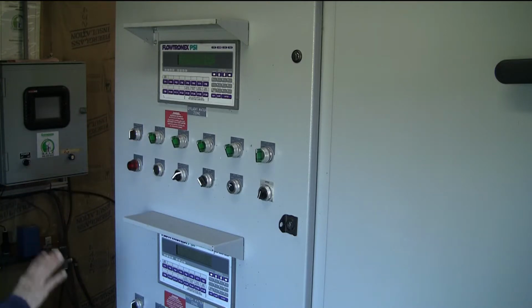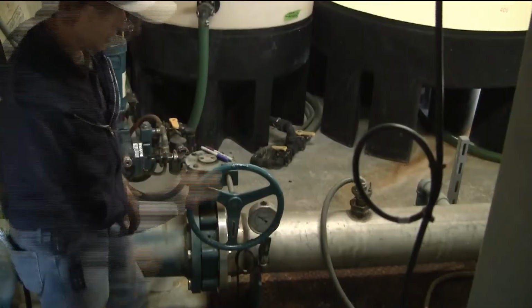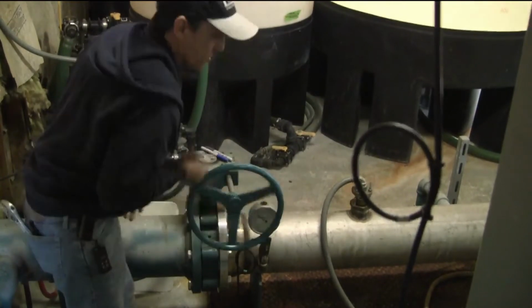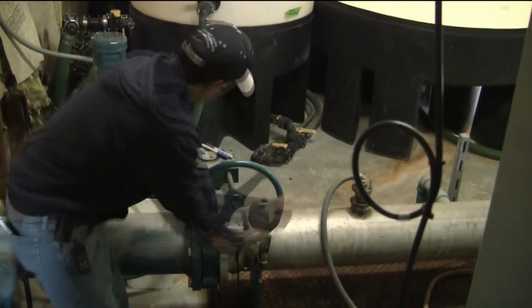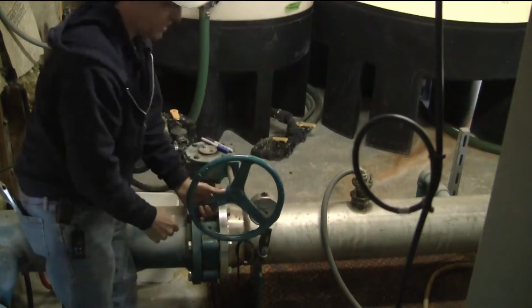I'm going to close the valve to the irrigation system. We're going to run the pumps just in the station to check the relief valve and adjust packing if necessary. Okay, closing the discharge valve. This one's nice, has a nice wheel on it. Sometimes you just have a dome.